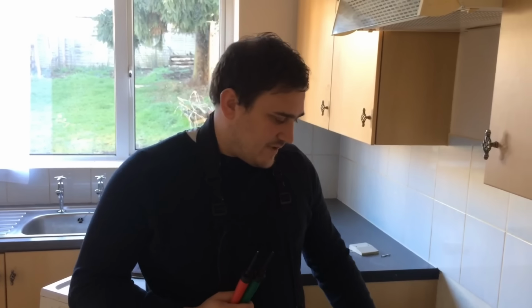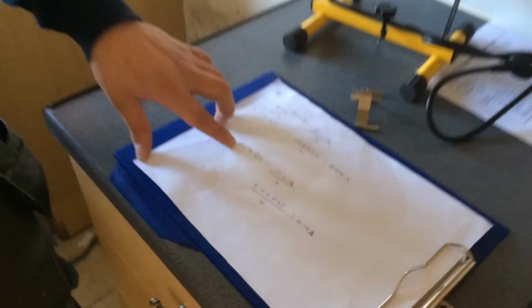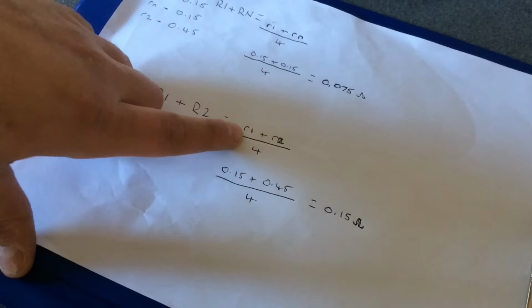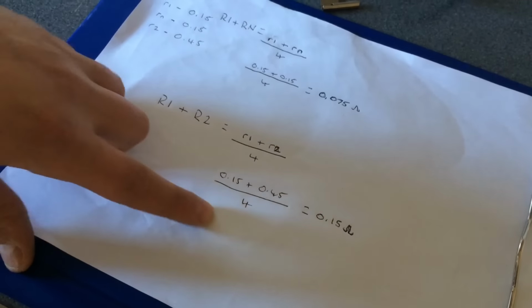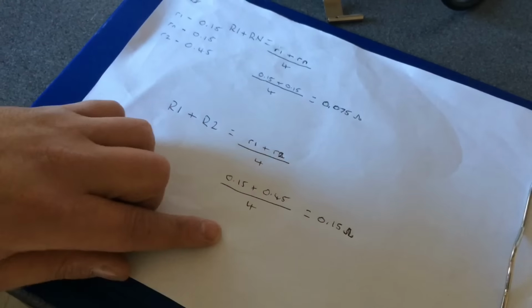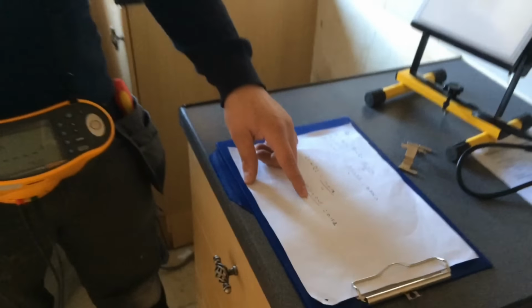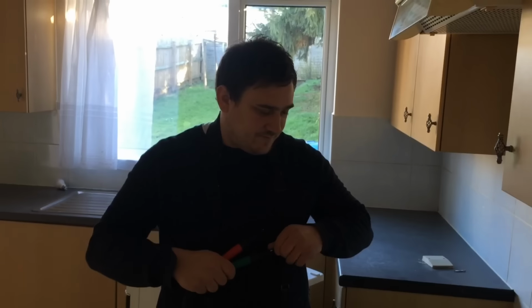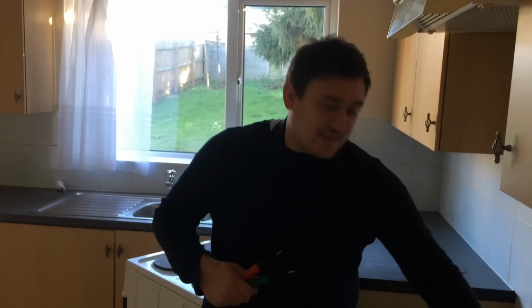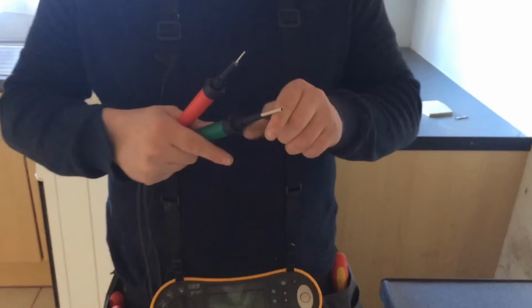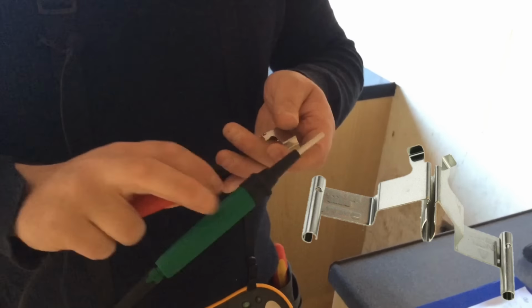Now we've finished the first part of our figure of 8 test, we're going to move on to the second part, which is our big R1 plus our big R2 equals our little r1 plus little r2 divided by 4, which gives us the reading of 0.15 ohms, which is slightly higher due to the CPC being a slightly higher size. First we're going to zero our lead so we can test in the consumer unit between the connector blocks.